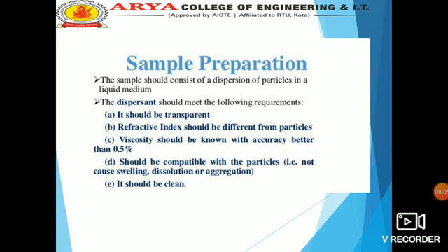The sample should consist of a dispersion of particles in a liquid medium. It should be transparent. The refractive index should be different from the particles. Viscosity should be known with accuracy better than 0.5% and the medium should be compatible with the particles, and the sample should be clean.